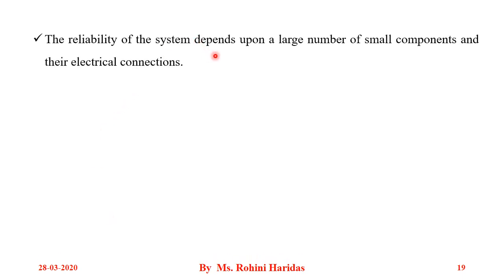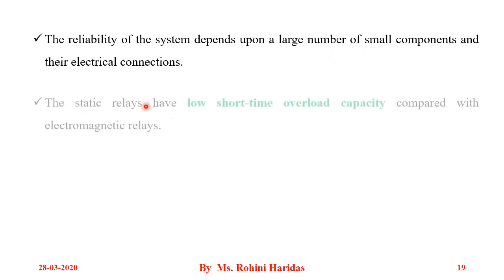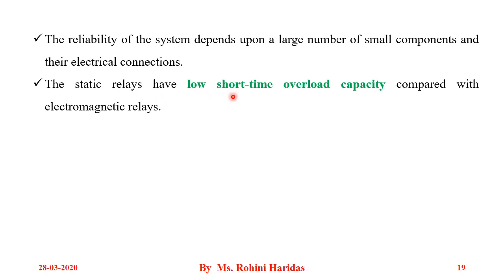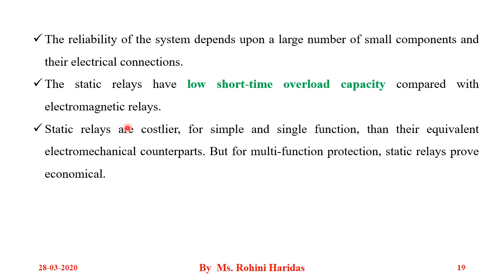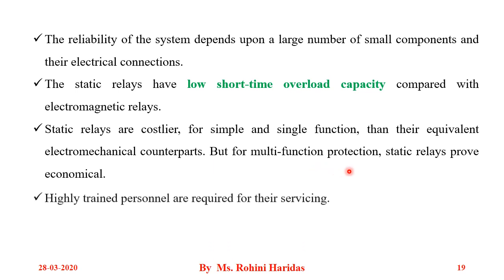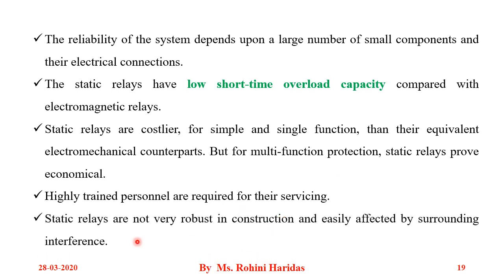The reliability of the system depends upon a large number of small components and their connections. Static relays have a low short-time overload capacity compared to electromagnetic relays. Static relays are costlier for simple, single-function applications than their electromechanical counterparts, but for multifunction protection, static relays prove economical. Highly trained personnel are required for servicing, and static relays are not very robust in construction and are easily affected by surrounding interference.